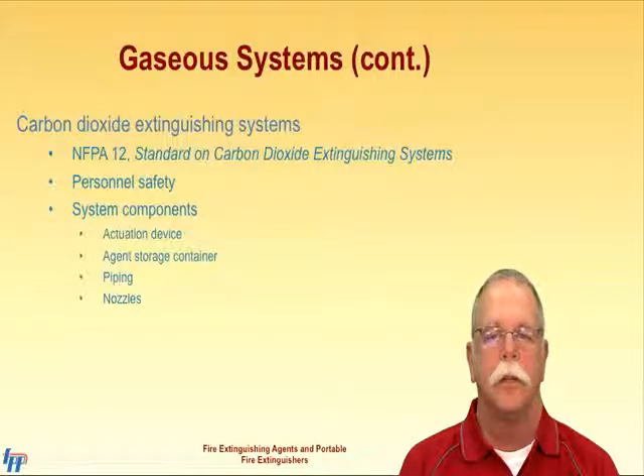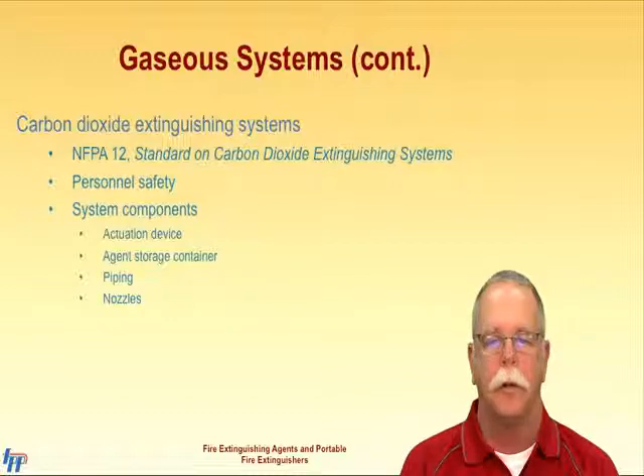CO2 can be set up to deliver the agent to a specific location or as a total flooding system. The risk with CO2 is that in the total flooding system configuration, the area becomes oxygen deficient, creating a risk for occupants and responders. These systems will be placarded and alarmed to notify occupants and responders that the system has been activated. CO2 systems may be designed to operate automatically upon detection of a fire or manually by occupant activation of a pull station.